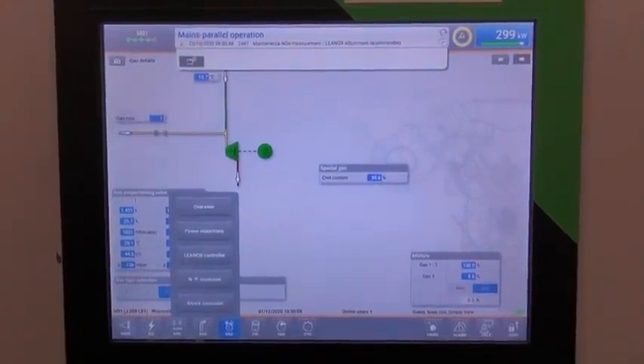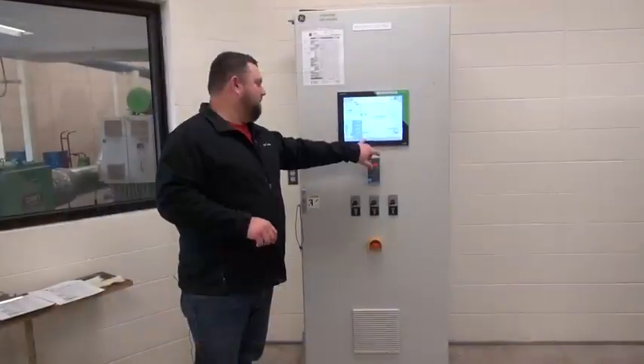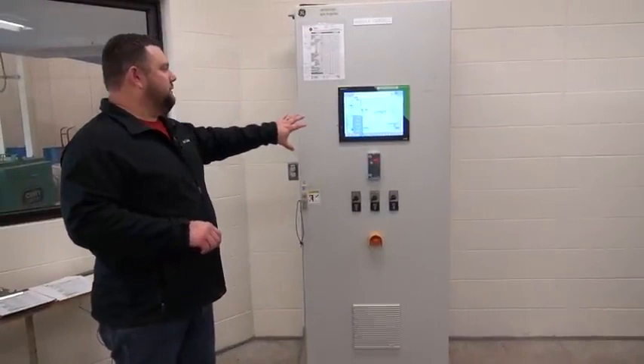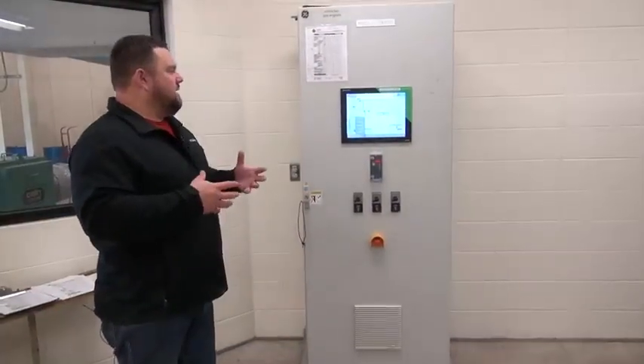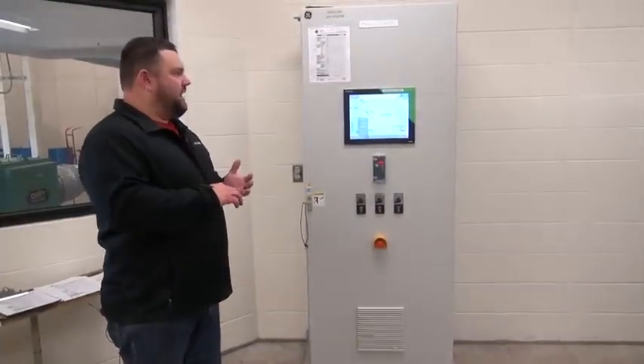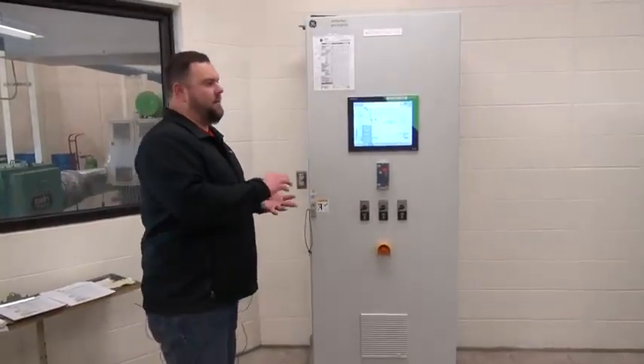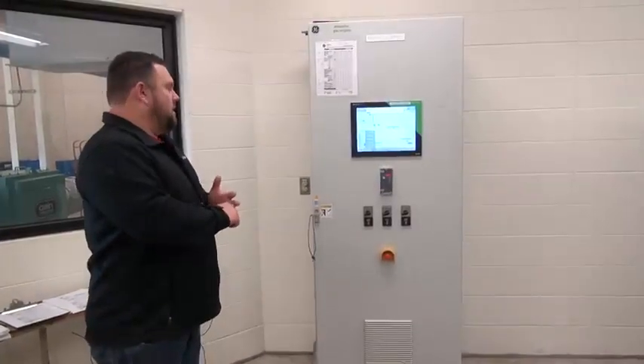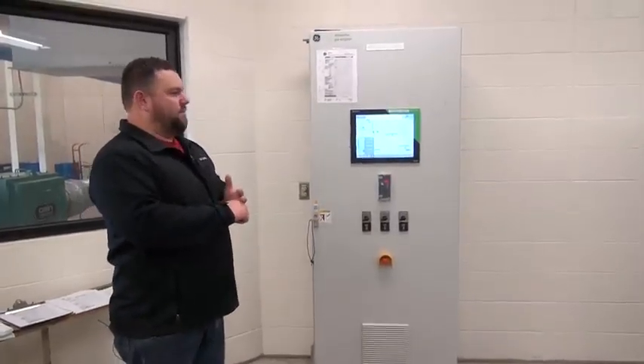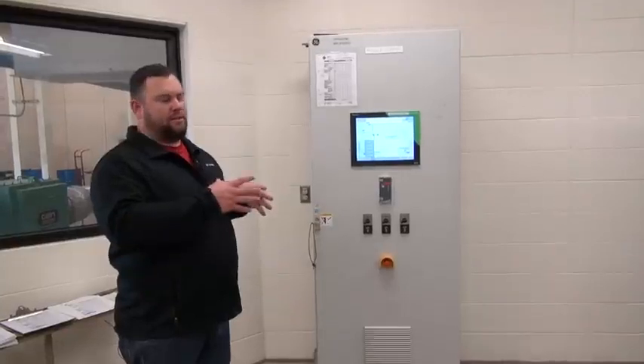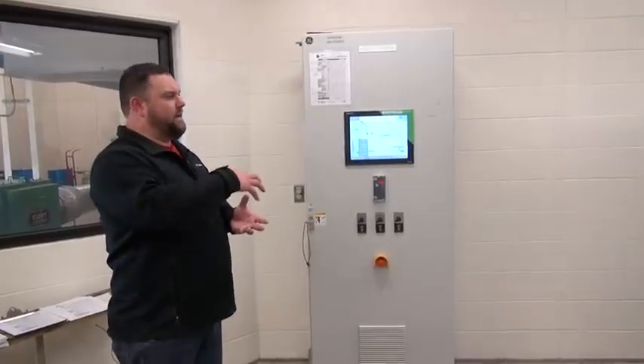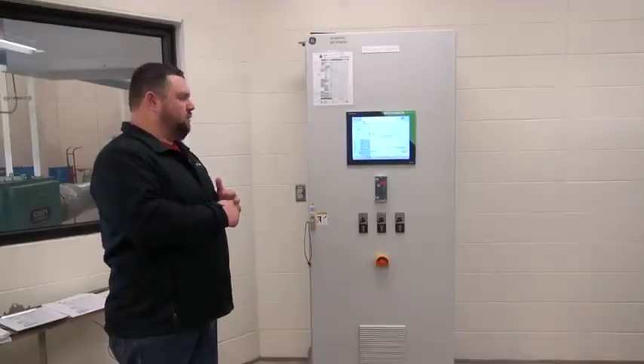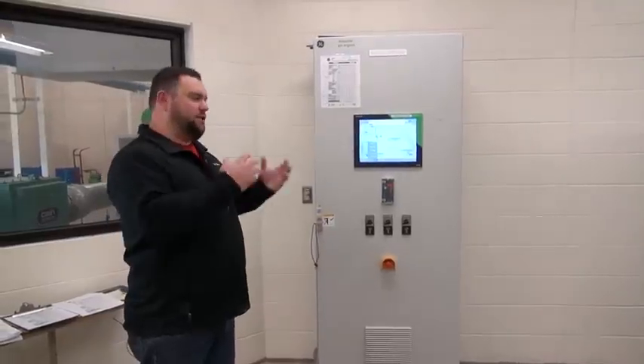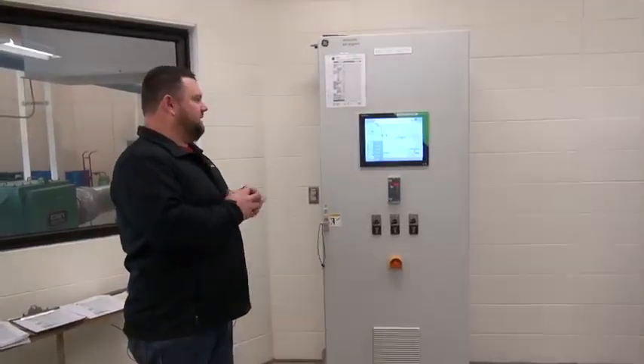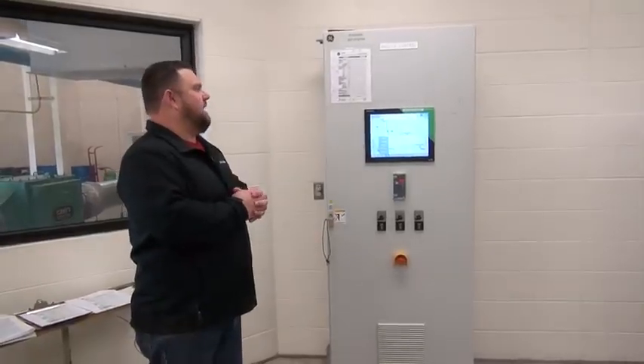I mean, it has more information than we can even really use. But it's a great tool for us to understand what's happening. One of the issues with burning biogas or methane is that it can be dirty, or it's dirtier than natural gas or diesel fuel. So we're dealing with cylinder buildup. You get what's called siloxane buildups on your cylinders and your cylinder heads. So we're always watching those temperatures to know when we need to pull those apart, clean them, change the spark plugs. There is a lot of maintenance that goes into this CHP type process.